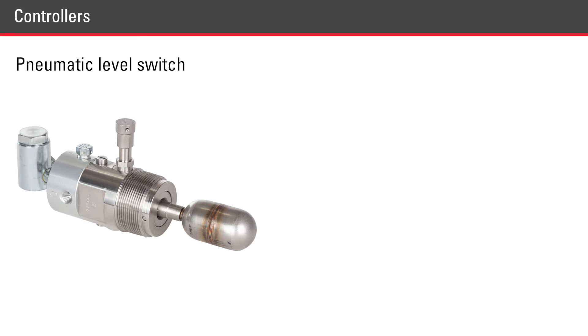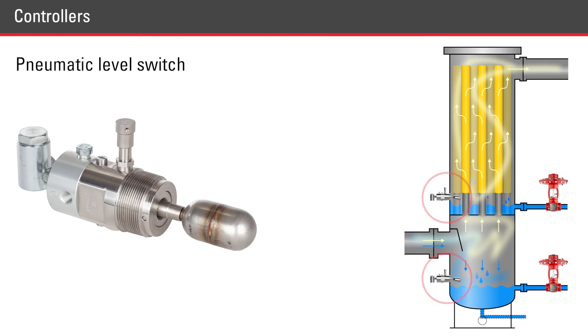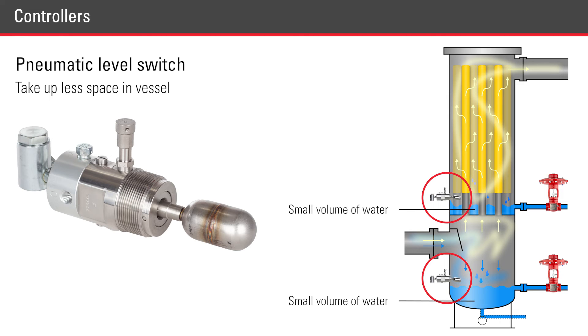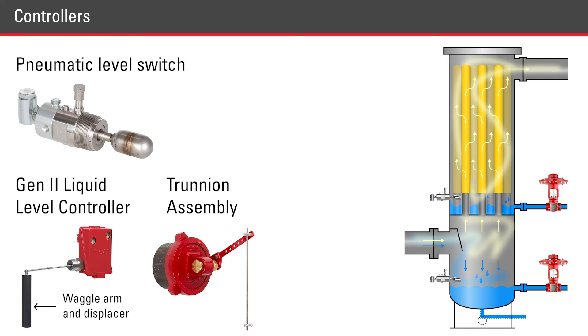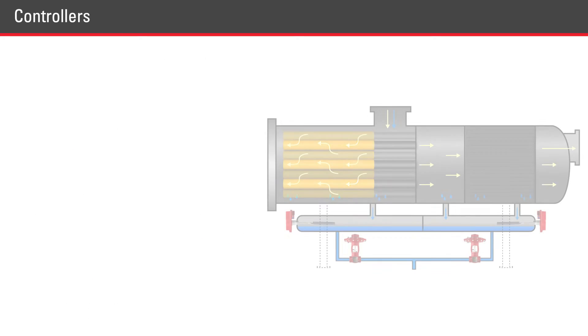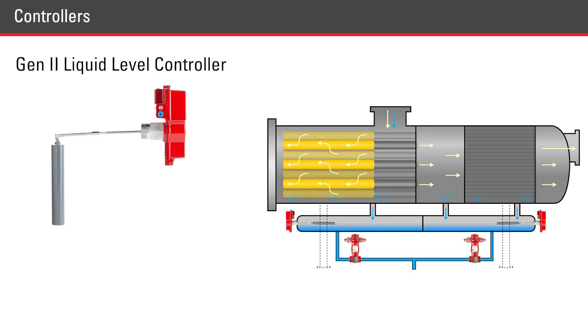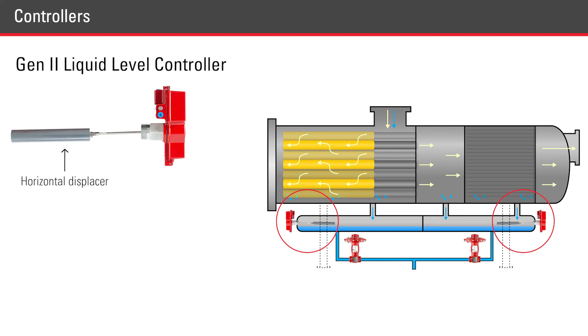Pneumatic level switches are ideal for a two-stage filter separator because they take up less space. The volume of liquids in the vessel is relatively small, and most of the space contains filter elements, leaving no room for the Gen2 level controller or a torque tube assembly for mechanical operation. In a horizontal filter separator, a Kimray Gen2 liquid level controller is an option because of the available space in the sump chamber of the vessel.